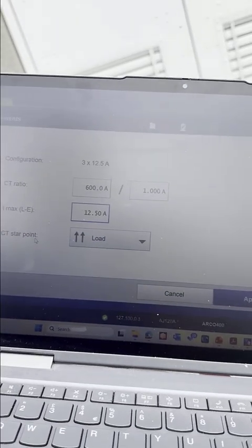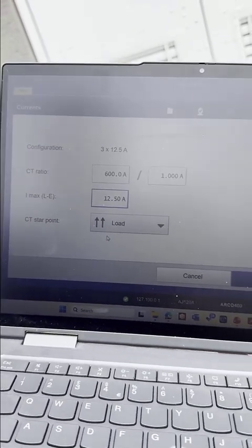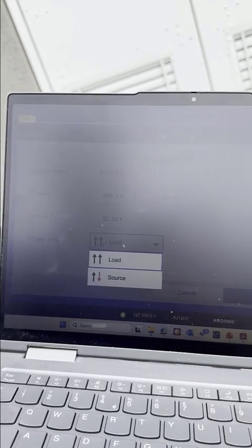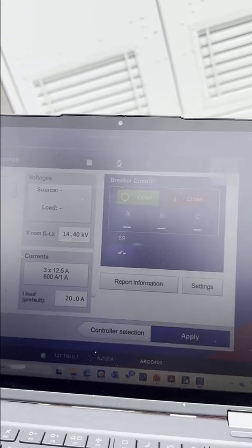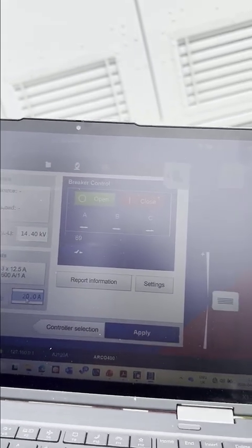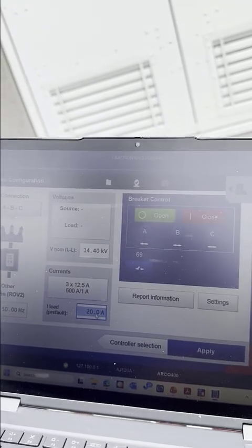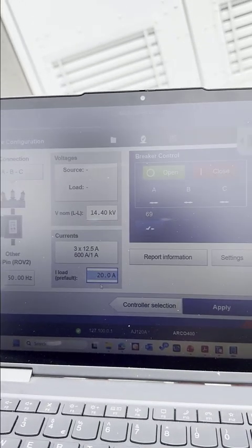And then you can specify the CT star point in case you have a directional overcurrent or directional earth fault. You can specify the CT star point, whether it is towards the load or towards the bus bar. Then you can click apply. Also here you have to define the load or pre-fault current to be used in some of the test modules, like sequencer, to be used as a pre-fault current, just to make sure everything is reset. And here is the breaker control, as you can see from the front panel. Also we have it here in the software.